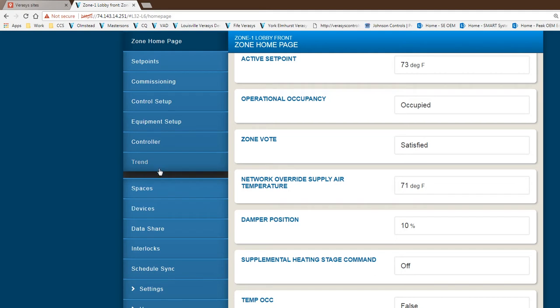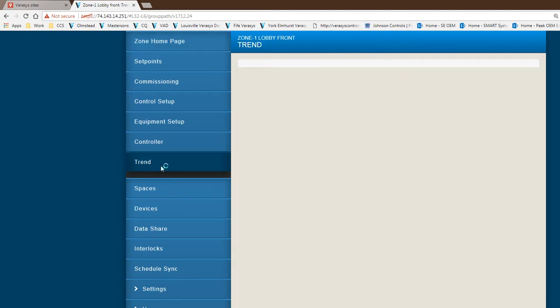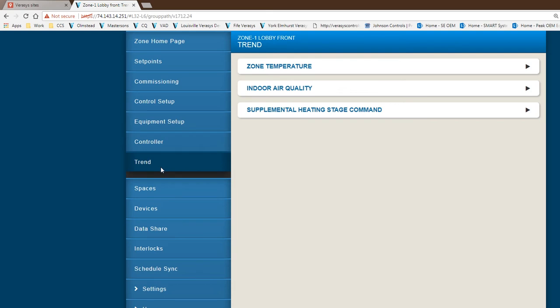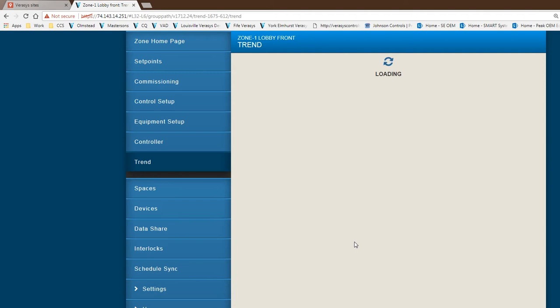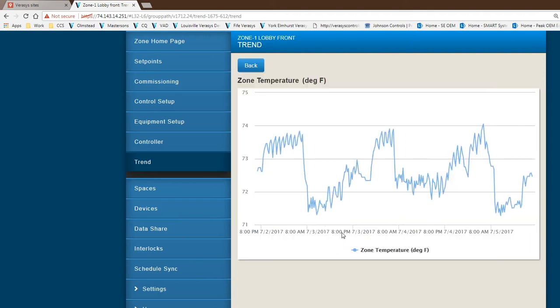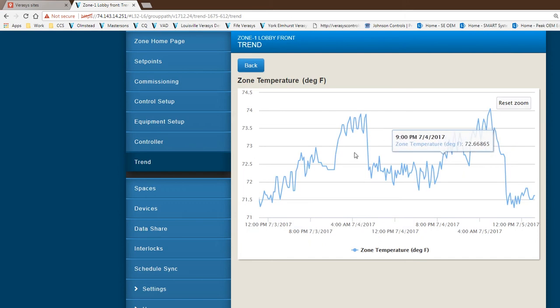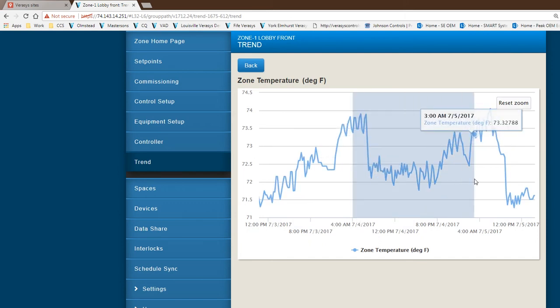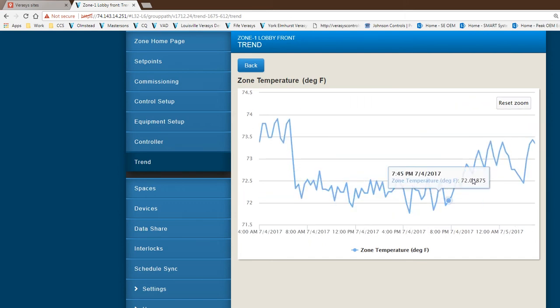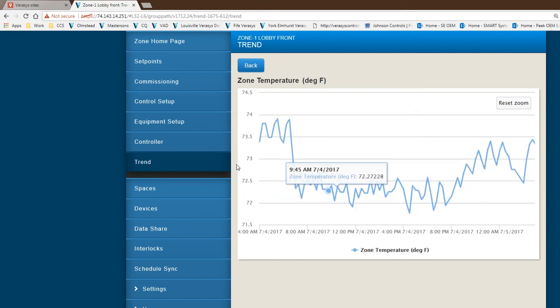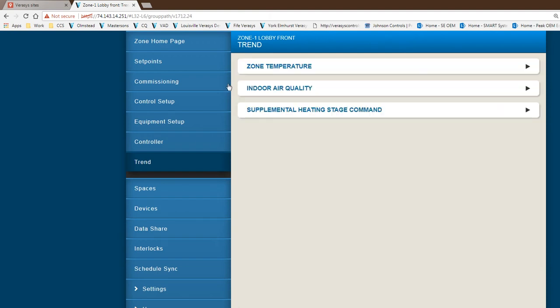The other function and features associated with every controller is what we call trend. Trend is always embedded inside our controller. As soon as you turn on the controller, it continuously starts holding trend information. In case of a zone damper, we have three values being trended every 15 minutes. You cannot modify this or add any trends, but it's a good service tool to come back and see what's going on with that particular zone damper at a certain time. We keep about roughly a day and a half to two days worth of data, and you can zoom in to certain sections to identify any issues.